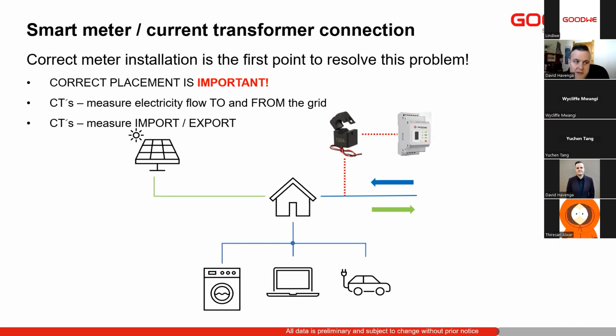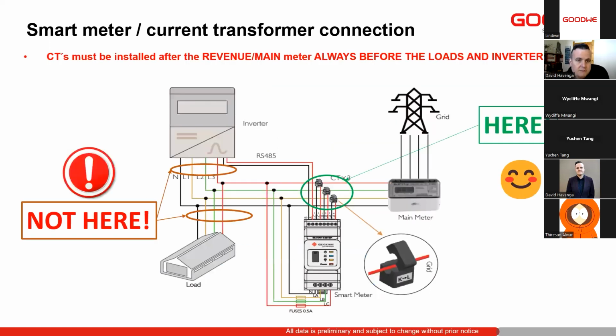So the CT is there to measure the electricity to and from the grid, especially for zero export. When we need to limit the power, it needs to be in the right place so we can see our non-essential loads. So the inverter can also provide us energy for the non-essential loads, as well as limit the export to utility. So with the three-phase, because I'm talking about the ET as well in this, but our installation here is only the ES, the three-phase meter is slightly more complicated to install. It's very important to make sure.